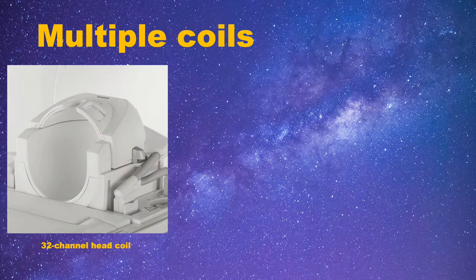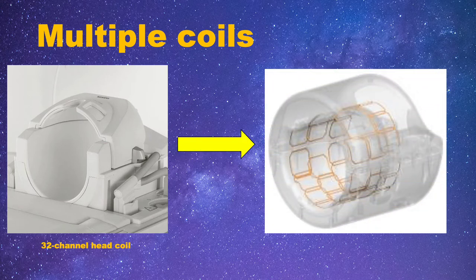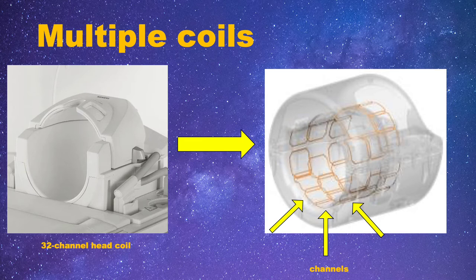Look at this picture of a typical head coil. Notice I labeled this picture as a 32 channel head coil. What does the channel here mean? Simply, it means there are as many as 32 small circuit loops inside the whole coil.